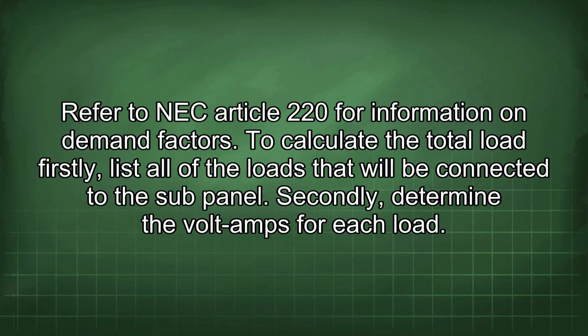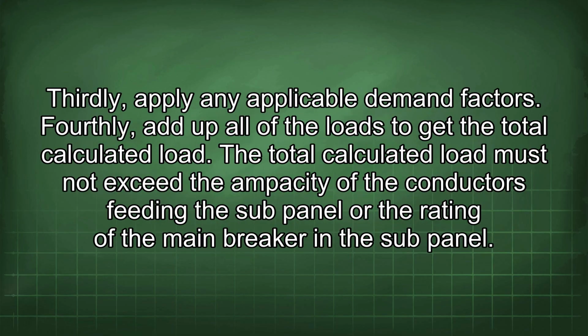To calculate the total load, firstly, list all of the loads that will be connected to the sub-panel. Secondly, determine the volt amps for each load. Thirdly, apply any applicable demand factors. Fourthly, add up all of the loads to get the total calculated load. The total calculated load must not exceed the ampacity of the conductors feeding the sub-panel or the rating of the main breaker in the sub-panel.